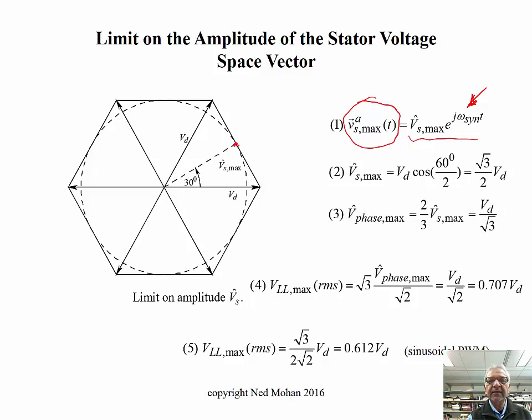So the limit occurs right here at 30 degrees from A axis over here. Because that's really the midpoint over here where the radius is the smallest at, compared to any other position of this desired space vector. So we can say that Vs max here is DC bus voltage times cosine of the 30 degrees, which is this value over here. So if that is the maximum that we can get for the space vector peak, and we know that the phase maximum peak is two-thirds of this here. So we get this value over here.